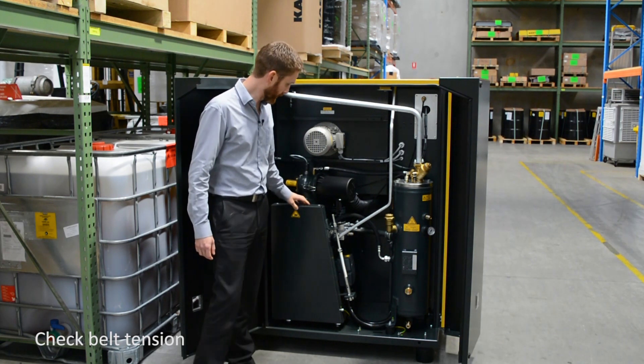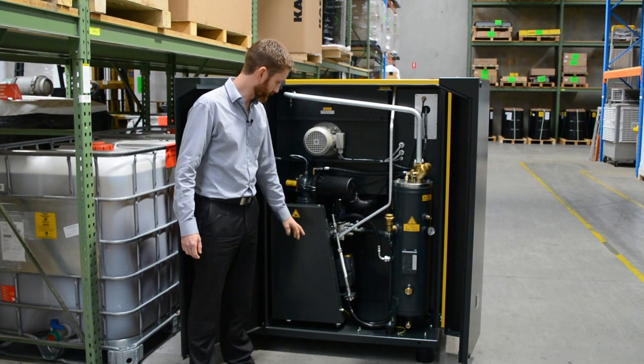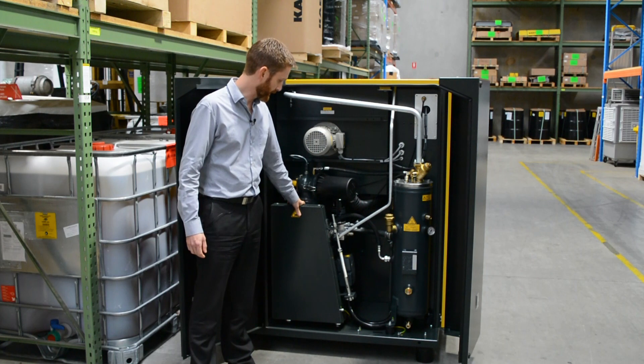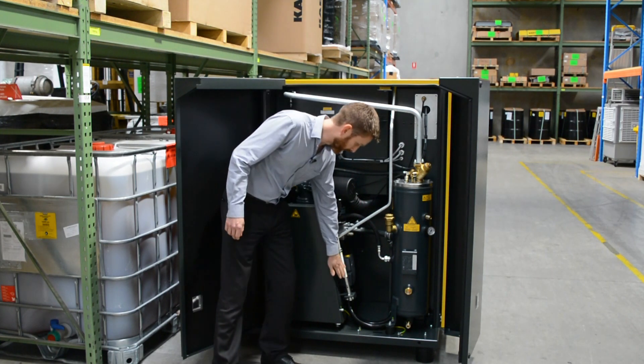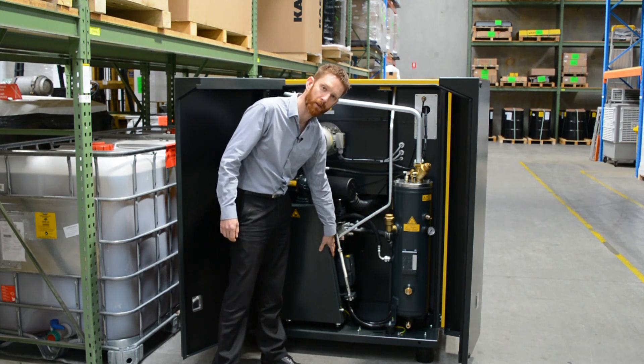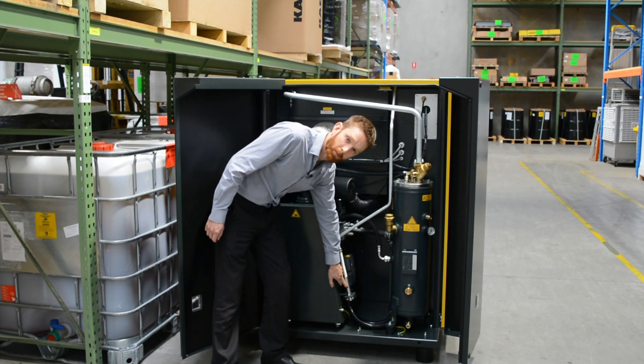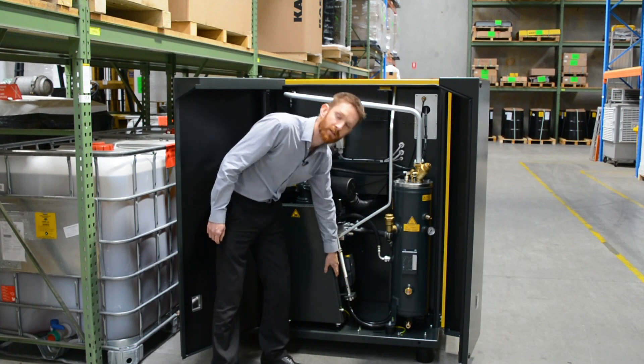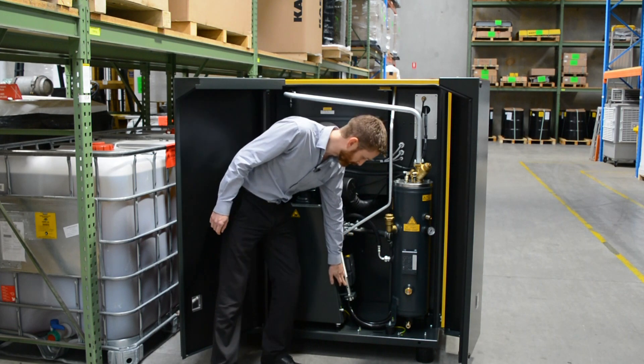The first item to check on a weekly basis is the belt tension and belt condition. The belt is located behind this guard on this machine — it connects the electric motor to the air end. You can check the belt tension on a Kaeser by looking at this guide here. We have a spring tension that tensions the belt, and this little peg in this elongated hole gives us an indication of how tight the belt is.